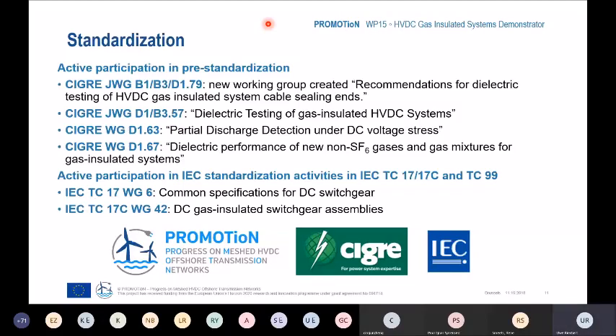Another important CIGRE working group is dielectric testing of gas insulated HVDC systems. So we had, especially about the long-term test and prototype installation tests, a lot of discussions with the CIGRE working group, and finally we have a common agreement on a procedure for this long-term test, as well as for all dielectric tests. Moreover, we had cooperation with the D1 community from CIGRE dealing with partial discharge detection under DC voltage stress, as well as with the group dealing with the dielectric performance of new non-SF6 gases and gas mixtures for gas insulated systems. And of course, we are also in contact with the new IEC groups dealing with the common specification of DC switchgear, and with the new group dealing with DC gas insulated switchgear assemblies, which will have its first meeting at the end of July.